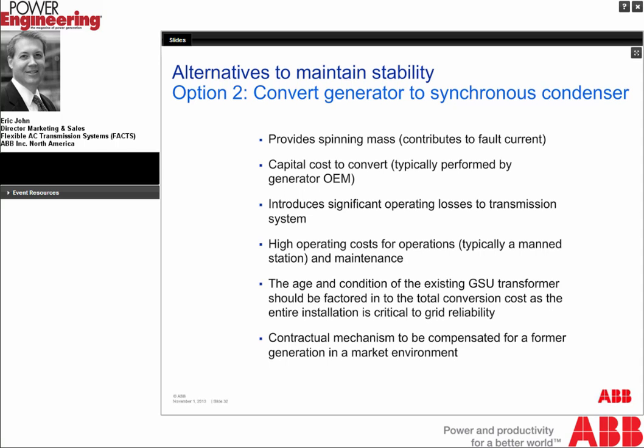So if we go ahead to the next alternative, which is to convert the generator to a synchronous condenser, the conversion will provide rotating mass, which means that it contributes to fault current. And this can have some technical benefits to the system, especially in physical locations where the system is extremely weak. John mentioned that in some of his study work, he's found systems where when the generator goes away, you lose that sort of anchor tenant on the system, and you can run into stability issues. By converting the generator to the synchronous condenser, you can maintain some kind of contribution to fault current, and that can have a benefit in terms of the overall system stability.